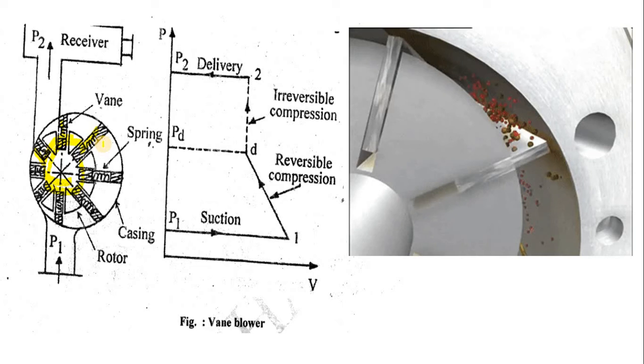The most important thing is that the eccentric rotor is connected to the electrical motor. When the electrical motor rotates, the shaft rotates and the eccentric rotor continuously rotates at very high speed. It creates suction in that particular suction line, and air comes in contact with the surface of the blade and the casing. Air is trapped in between the vanes and casing. In the slots, spring loaded vanes are placed, whose main purpose is to allow the compression and extension action when it moves continuously in the clockwise or anti-clockwise direction.